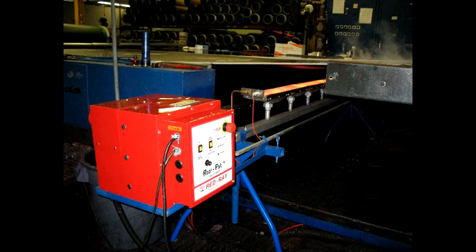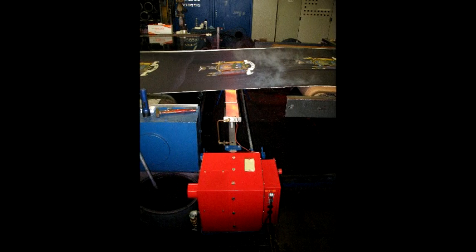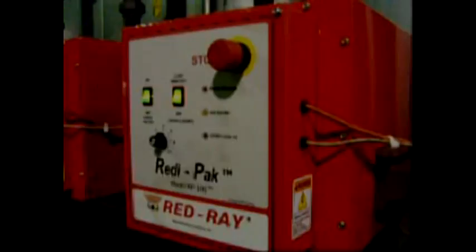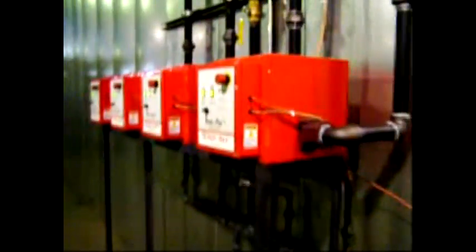A burner and its controls can easily be placed under or over a web for process heating. Here's an example of a single burner in a textile drying application. Burners can be added to ovens individually with one Redi-Pak per burner array. Here's an example of infrared burners added to the entrance of a powder curing oven. There's a maximum of 150,000 BTU per hour per Redi-Pak, which will operate a burner of up to 7 feet long.